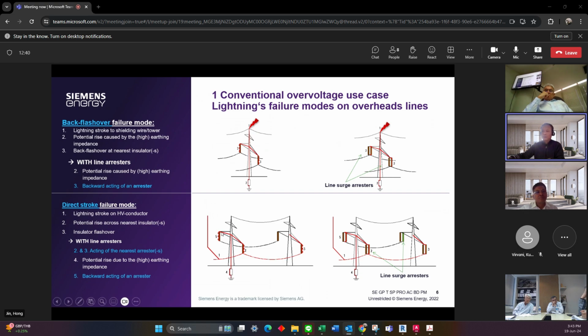So both cases, back flashover and direct stroke, can be avoided by the surge arrester itself. If we install line surge arresters in parallel to the insulator, when the lightning strike comes again to the tower or to the shielding wire, and this overvoltage happens across the cross arm and the transmission line, very quickly, within a microsecond, the surge arrester will be active. This means the surge arrester becomes conductive to discharge the current from the cross arm to the transmission line, and to limit the overvoltage, because the surge arrester has a residual voltage that can limit the overvoltage below this level. We call it the protection level of the surge arrester, and it is much lower than the insulator withstand voltage.